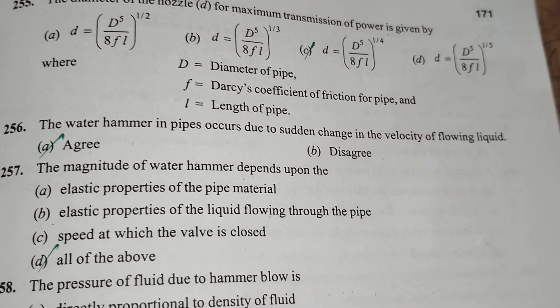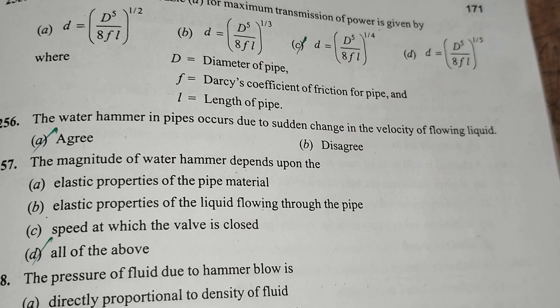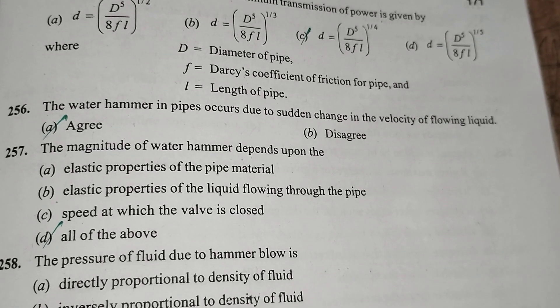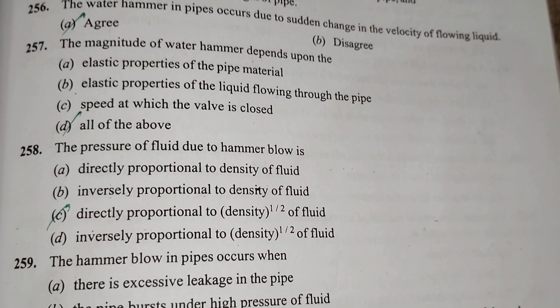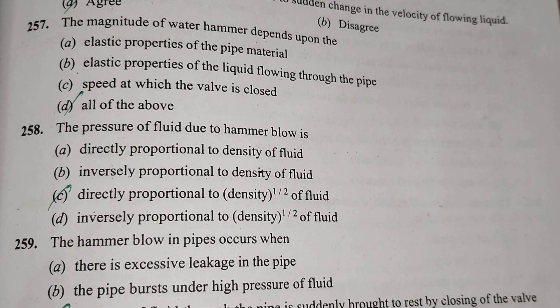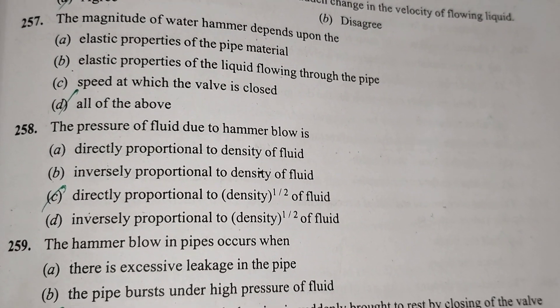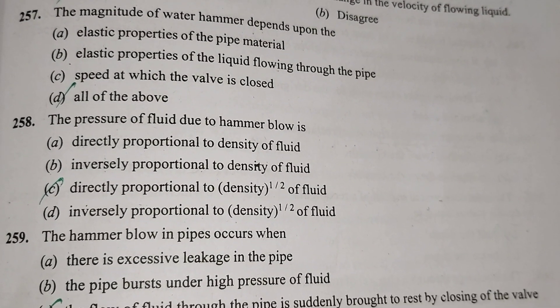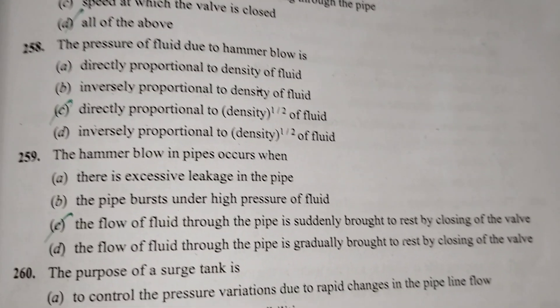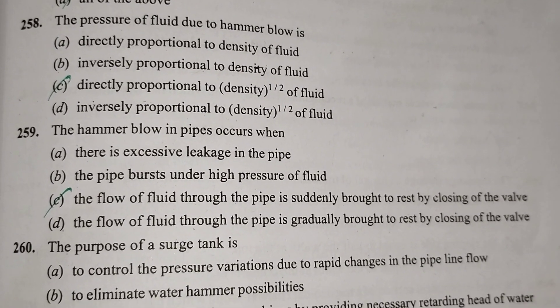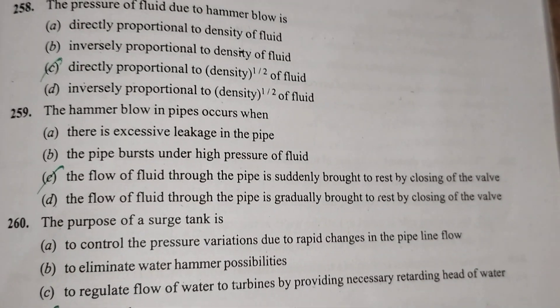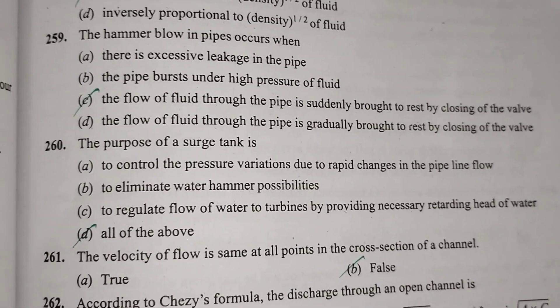Water hammer in a pipe occurs due to sudden change in the velocity of flowing liquid — Agree. The magnitude of water hammer depends on all of the above factors. The pressure of fluid due to a hammer blow is directly proportional to the density of liquid. A hammer blow in a pipe occurs when the flow of liquid through the pipe is suddenly brought to rest by closing a valve. The purpose of a surge tank is all of the above.